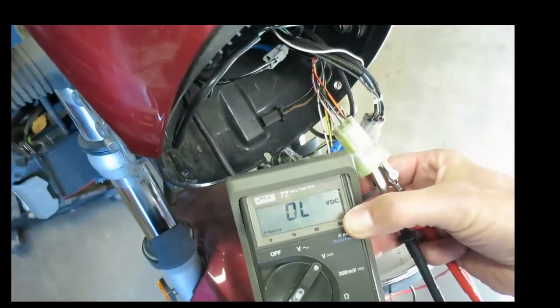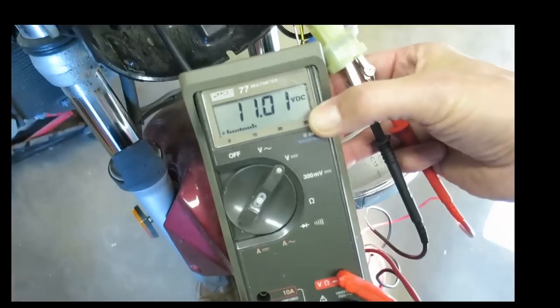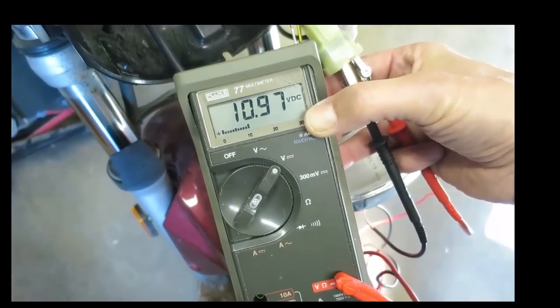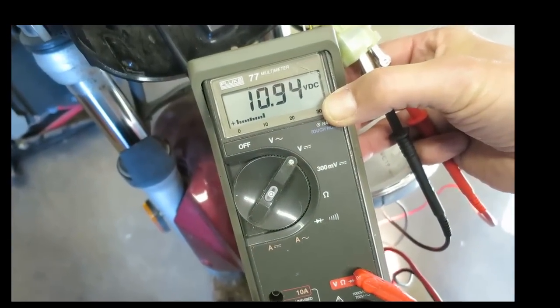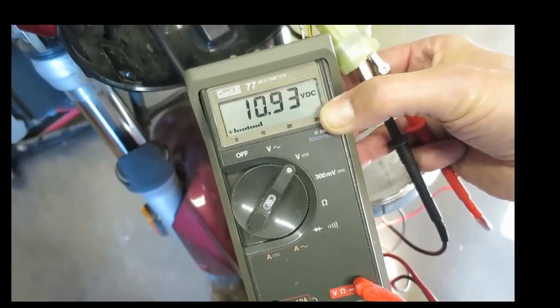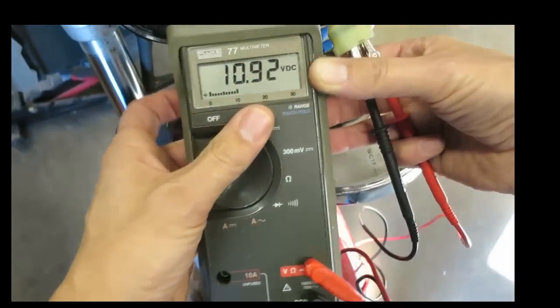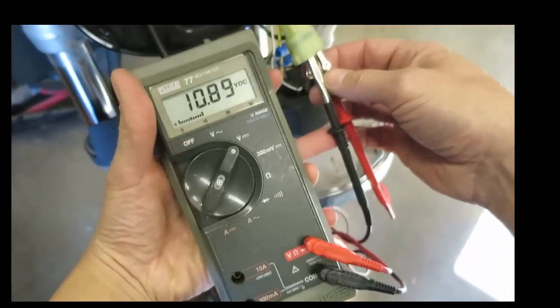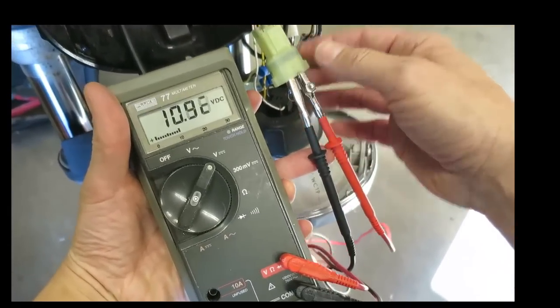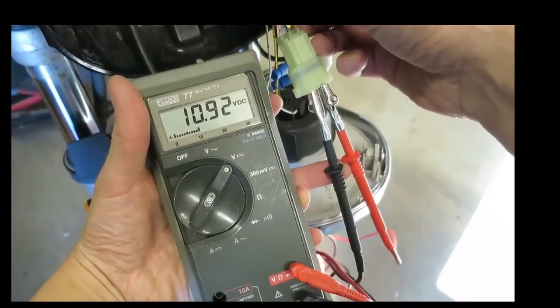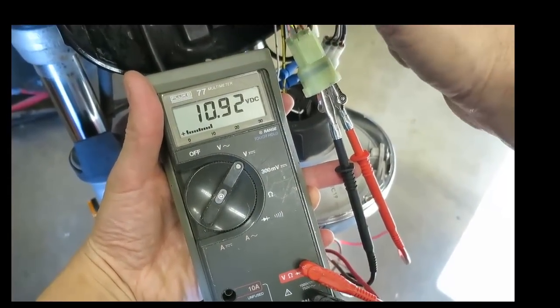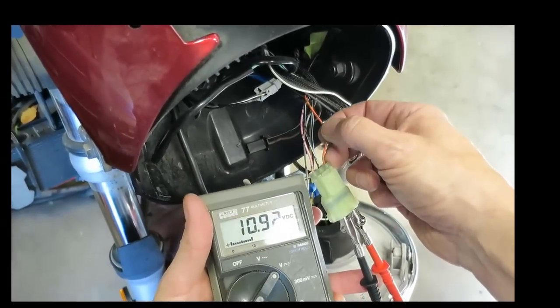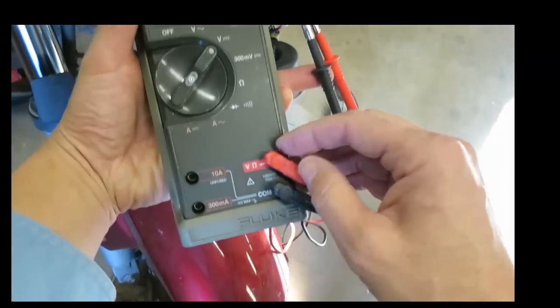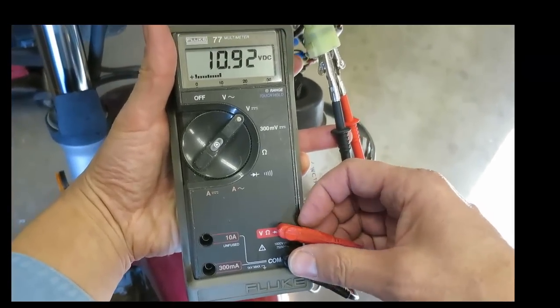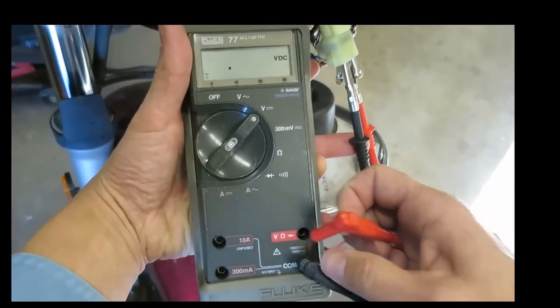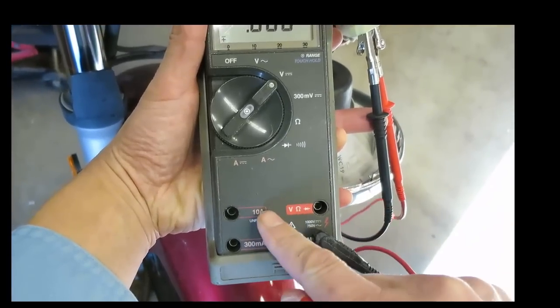So we're going to turn power on, and we see 11 volts. This is a little bit under battery voltage due to the source coming through the gauge, not directly from the battery. Now another test we can do while we have this hooked up is we can measure the current coming out. Now there is, as said, a 100 ohm current limit resistor from the gauge in this orange red line here. So if we put the meter into current measure mode, we unplug the red, and then down here there are two settings.